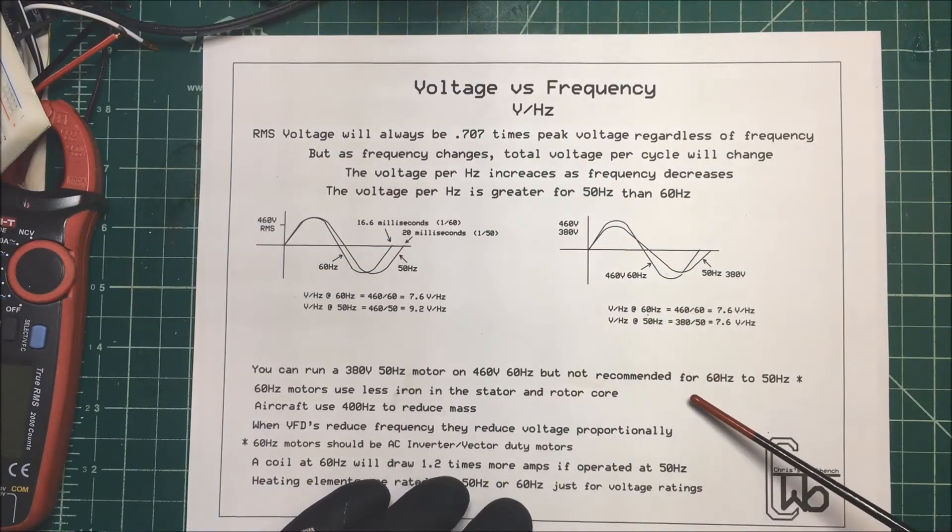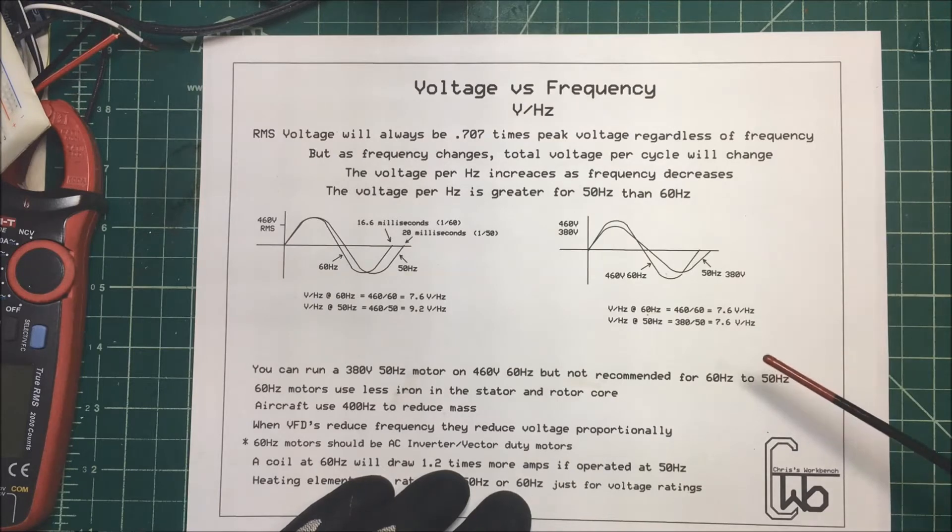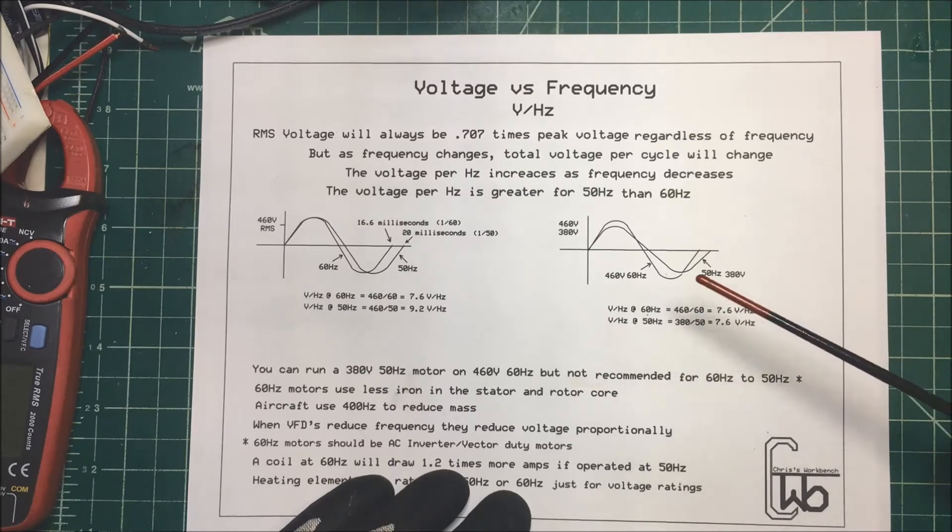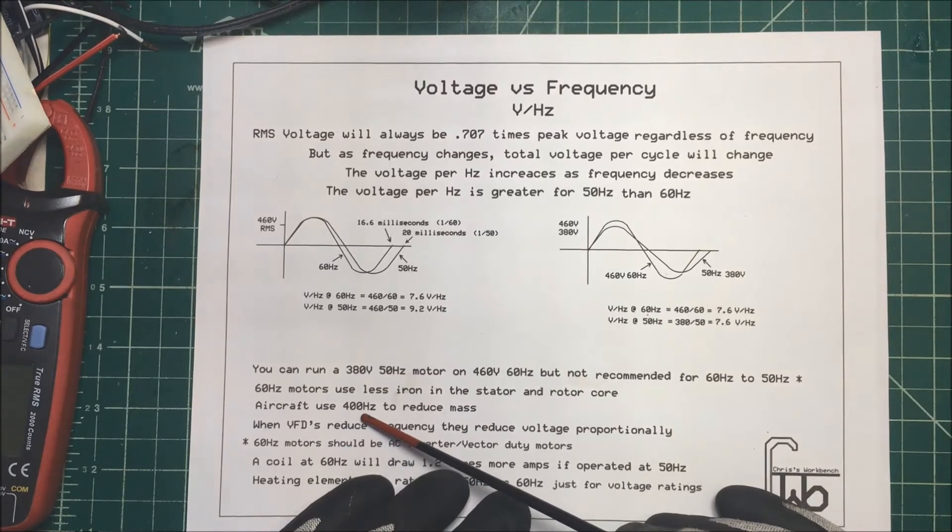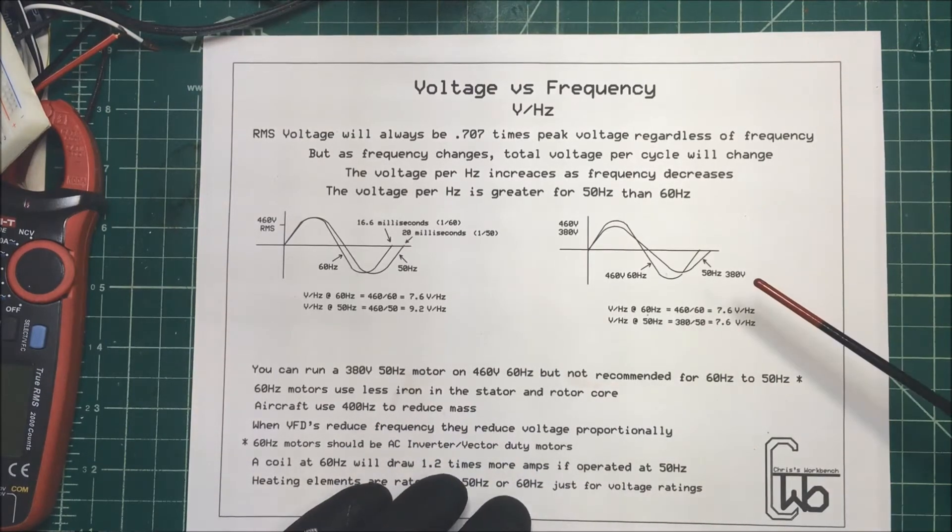Now it's not really recommended to run a 60 hertz at 50 hertz because a 60 hertz motor has less iron in the stator and the core. The higher the frequency you can use, you can use less iron. So aircraft use 400 hertz just to reduce the mass.